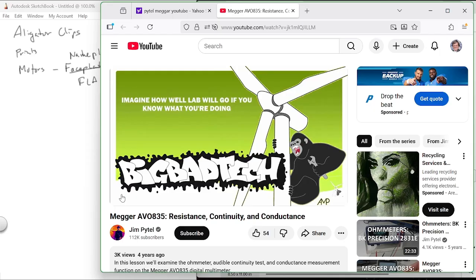Is that like the digital multimeters we have in the lab or not? Is a megger equal to a digital multimeter or not? It's not. The old style meggers, I'll give you a clue, were nothing more than the old telephone ringer that jacked up the voltage to 500 volts. I don't know if these use 500 volts, but the old style did. Very low current, but a very high voltage, and they tested at high voltages so that you would actually see if it was working at high volts.